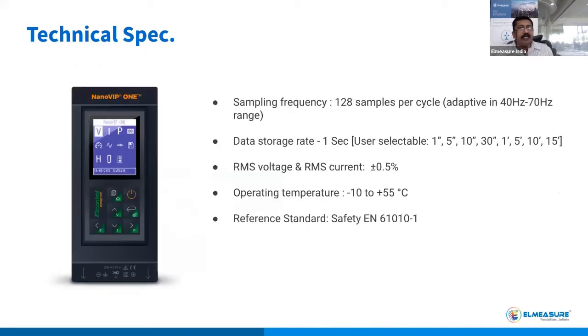Sampling frequency is 128 samples per cycle, which is used at 40 to 50, 70 hertz, we can say. So it's taking 128 samples, and then you can store data from 1 second up to 15 minutes: 1, 5, 10 or 30 seconds, then 1 minute, 5 minutes, 10 and 15 minutes. You can select it and you can do the campaigning there. Okay, and then you can store the data in the 4 GB memory and you can do the analysis.